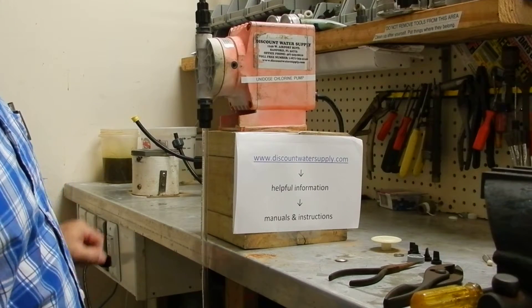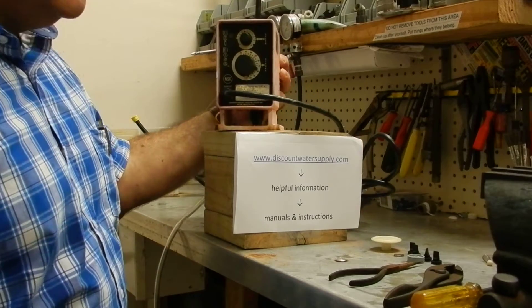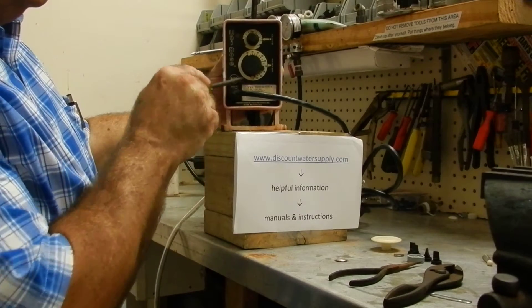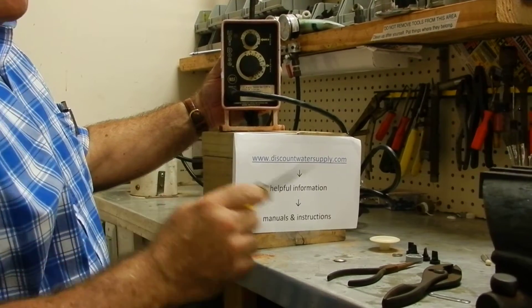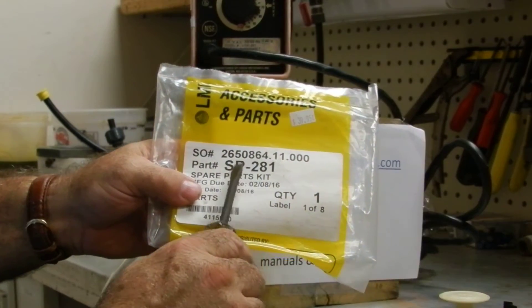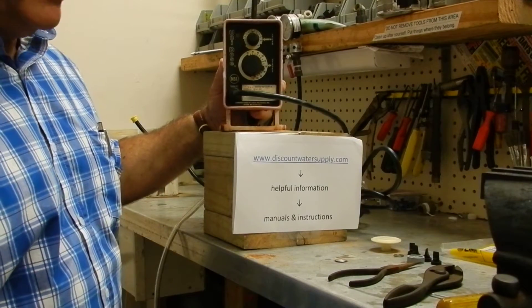I'm going to show you how to rebuild a Unidose chlorine pump. This is the model U141-281. Any pump ending in 281 can be rebuilt with the SP281 parts kit. If the model includes the letters TU or TT, you need a different set of parts.